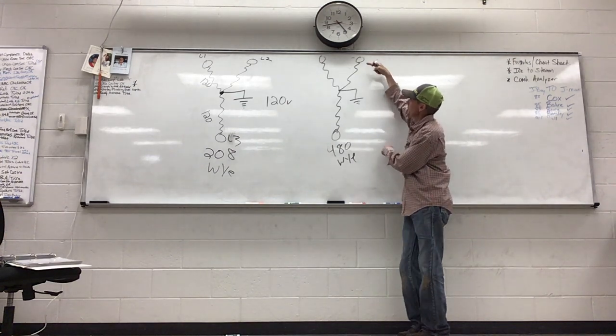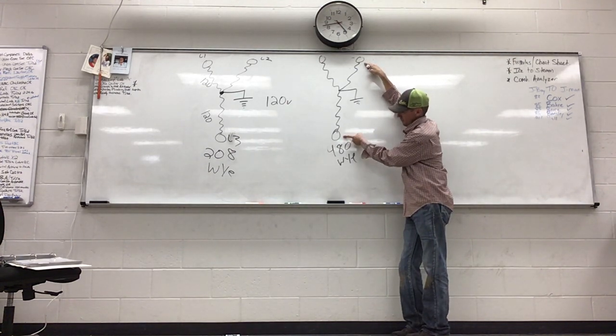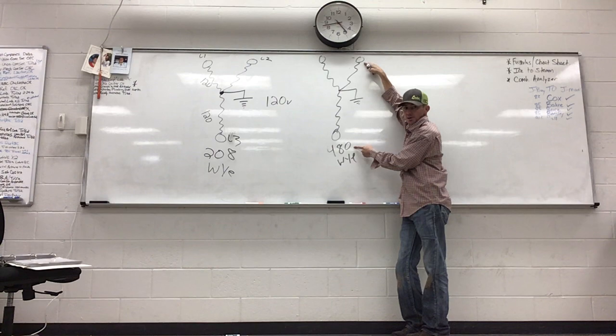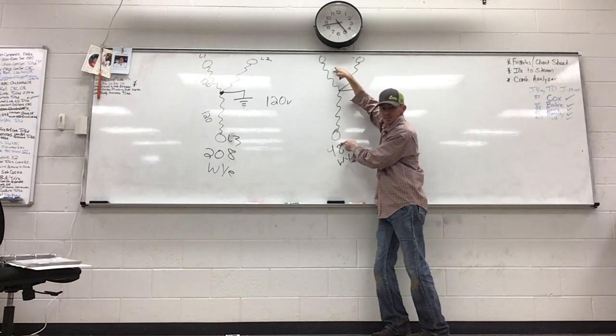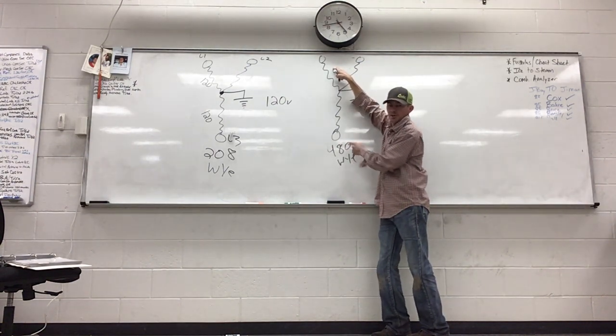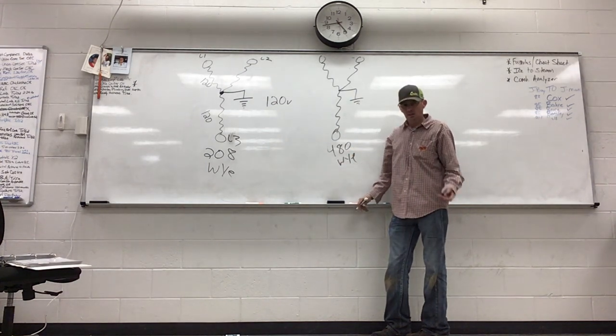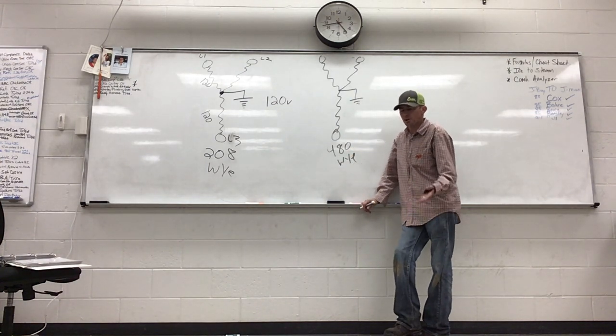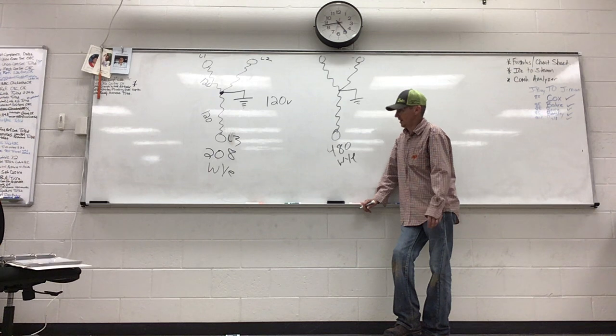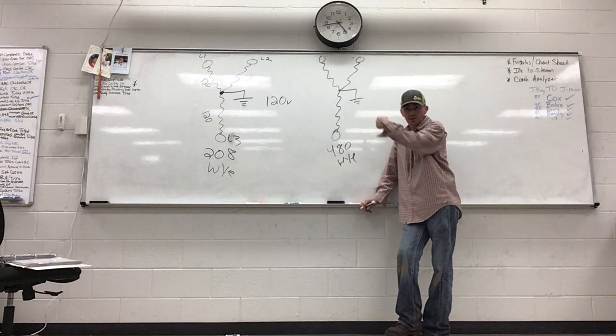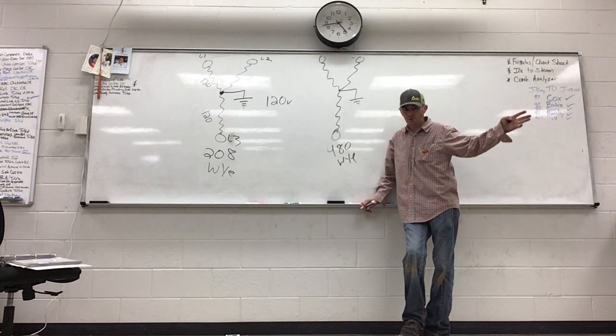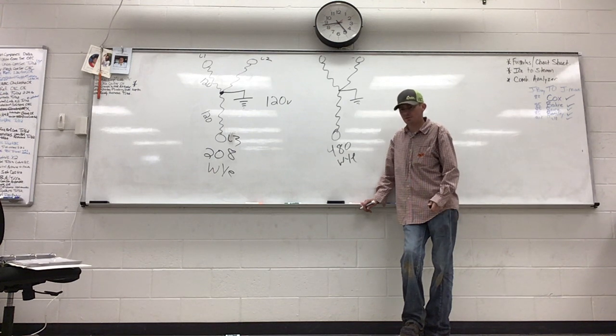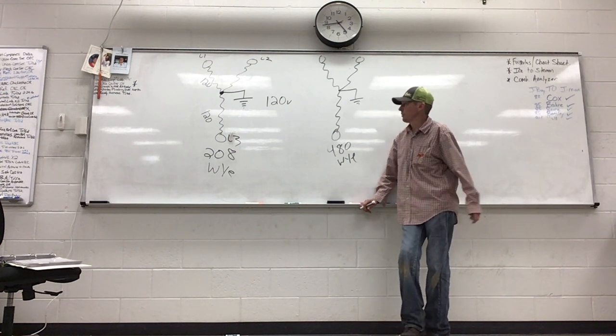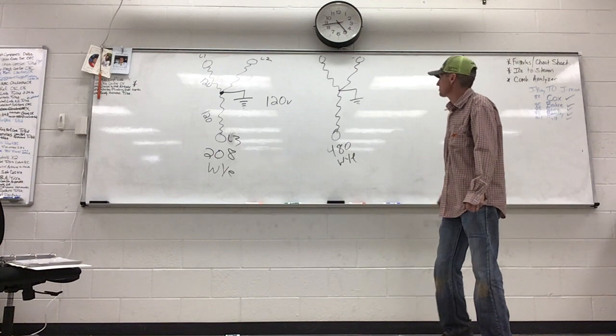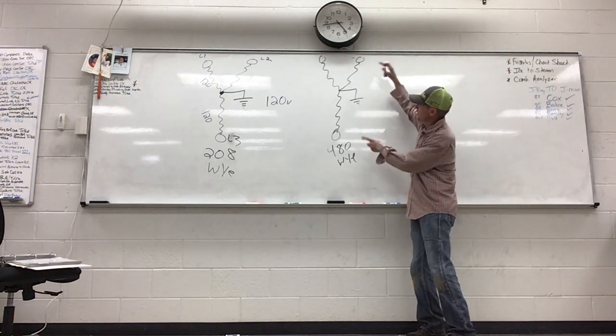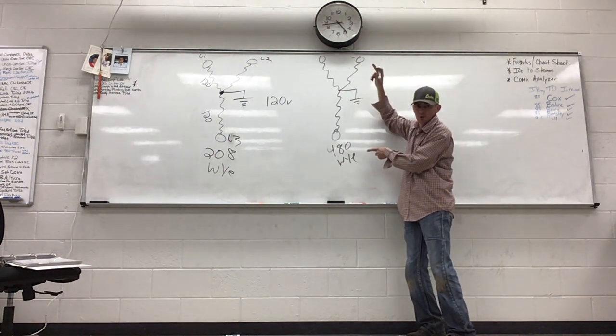So guess what? If I go from leg to leg, I'll get 480. If I go from any leg to any leg, I'll get 480 volts. 460, 480, plus or minus 10%. If we step over here to the Reynolds building right now, I guarantee it's running at 500 volts. It always runs high, so anyways, 480 plus or minus 10%. Leg to leg, any leg to any leg, I'll get 480.